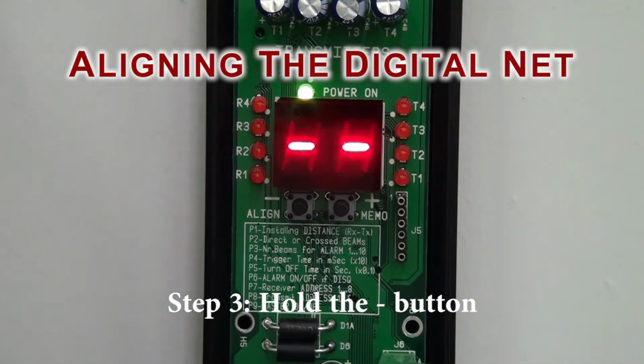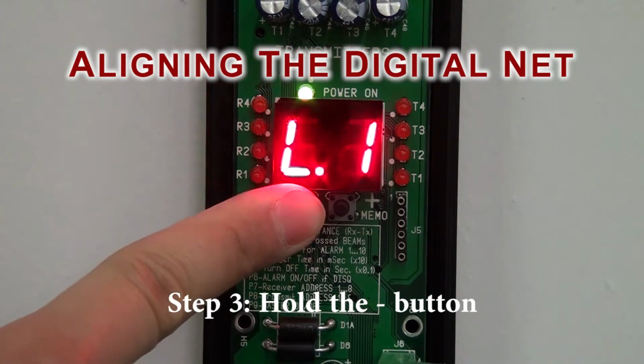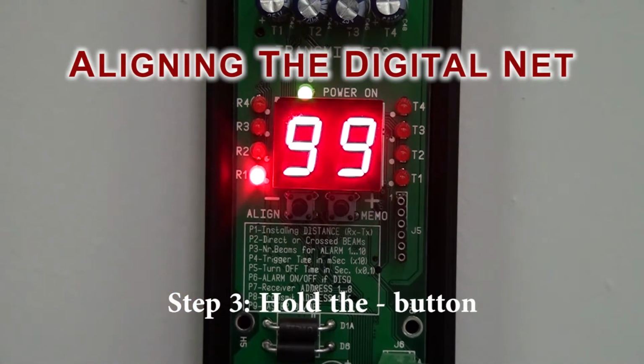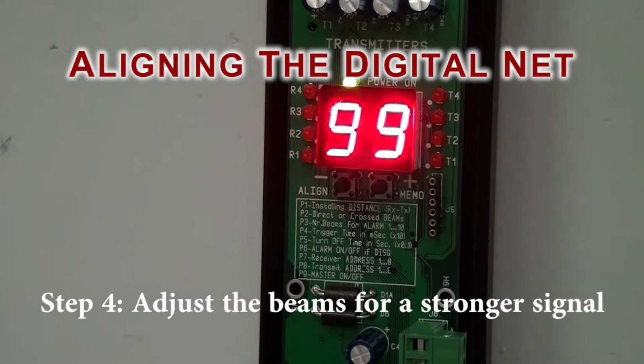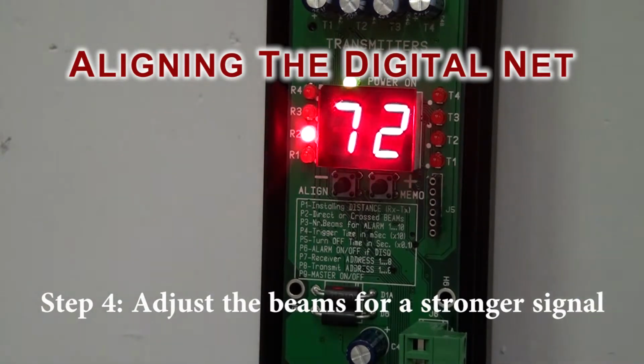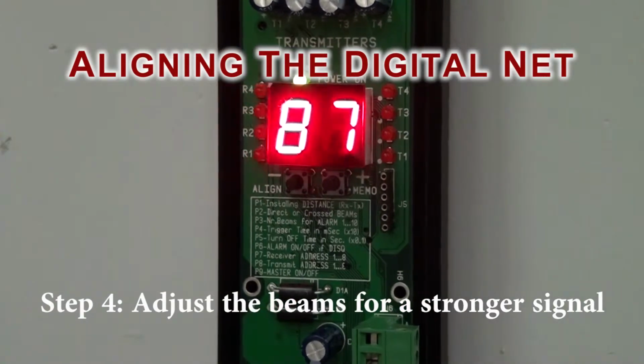Hold the minus button until R1 starts blinking. Doing so will enter alignment mode. Here you can see the value ranges from 0 to 99. This is the signal strength, and 99 is the maximum value. Pressing the minus button will switch between photo eyes. Right now the signal strength is about 71. If we break the beam, the barrier will still work, but we could get a stronger signal.